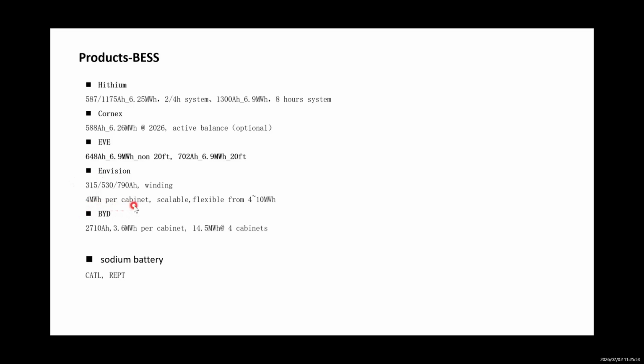So with this solution you can go from 4 megawatt hour up to 10 megawatt hour capacity, which is the maximum for a single unit, because these single units use the same chillers and cooling units. So it's like a 4 megawatt hour battery container, another 4 megawatt hour battery container, and the last battery container is 2 megawatt hour, all with the chillers integrated into a single unit with maximum capacity of 10 megawatt hour.